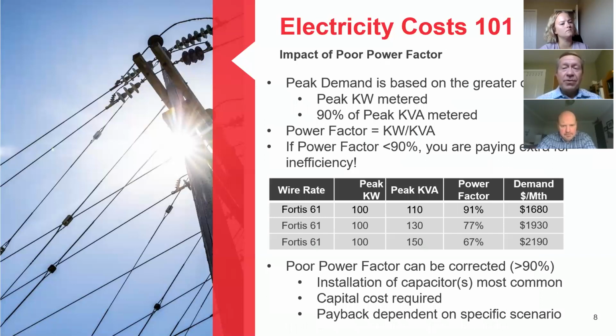So one of the other things that can result in additional costs is if your equipment has a poor power factor. For most of the wire's delivery rates for small and commercial or larger customers, the peak demand is also based on the greater of the actual metered peak measured in kilowatts during the month, or 90% of the actual metered peak measured in kVA. So the meter records typically both kilowatts and kVA, and it will set your peak demand and the amount you bill on based on the higher of the two.